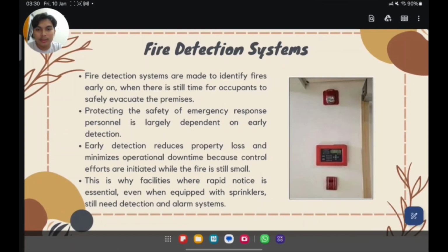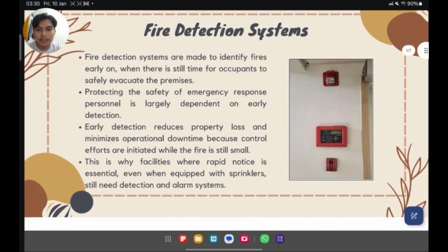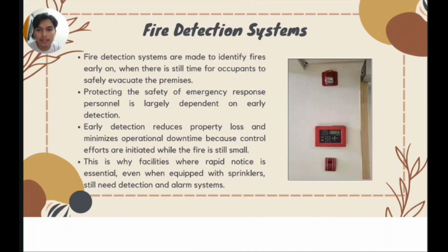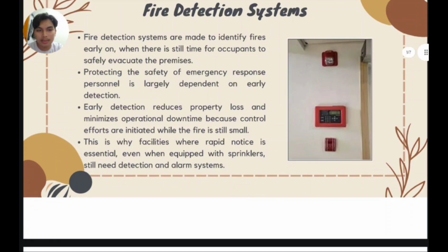Okay, now for the fire detection system. Fire detection systems are meant to identify fires early on when there is still time for occupants to safely evacuate the premises. Protecting the safety of emergency response personnel is largely dependent on early detection. Early detection reduces property loss and minimizes operational downtime because control efforts are initiated while the fire is still small. This is why rapid notice is essential; even when equipped with sprinklers, you still need detection and alarm systems.